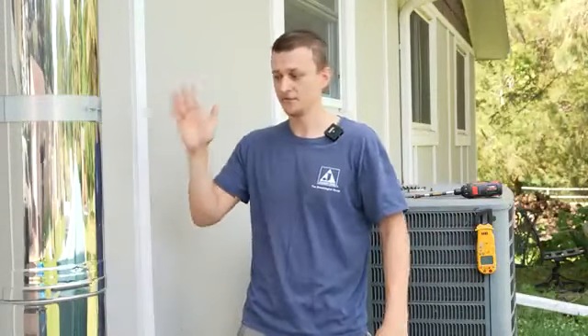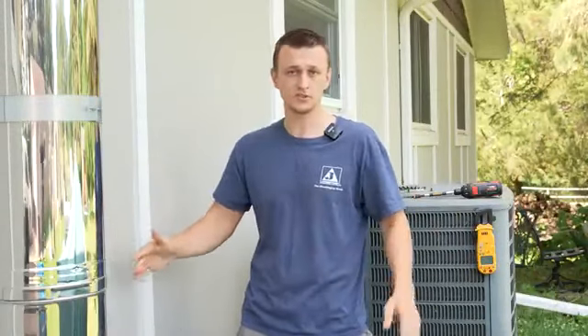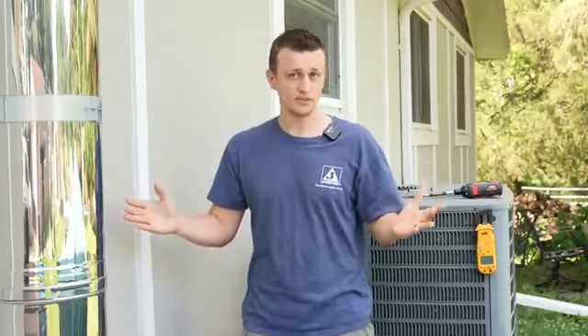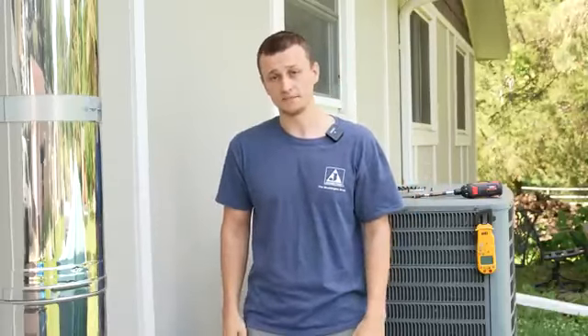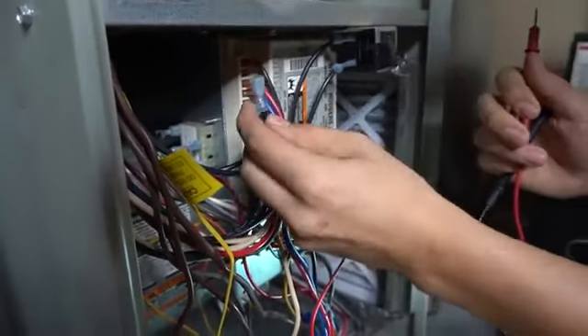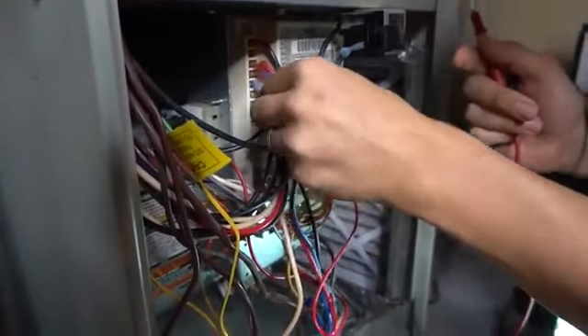Another symptom could be that the fan motor just stays on all the time in the furnace. So regardless of what you turn off or on, the fan inside just runs and runs and runs. It's stuck in the on position. So the control board can do funky stuff like that. If your furnace is doing some bizarre things, then perhaps that control board is bad. I have a video where I show you how to simply troubleshoot the control board and see if there's anything wrong with it.